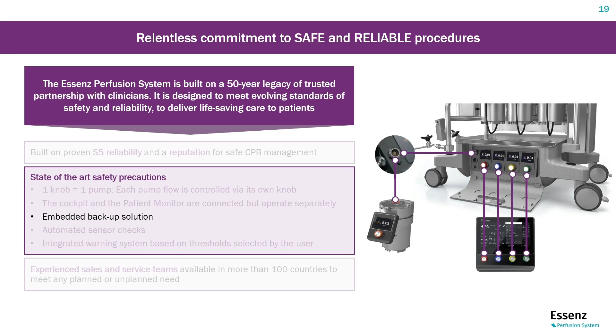In order to ensure that all the sensors are ready and up to run, a safety sensor check has been introduced. Bubble, flow, level, pressure sensors can be checked up front, before starting the case. All of this is to provide you the peace of mind to manage cardiopulmonary bypass procedures in a safe way.